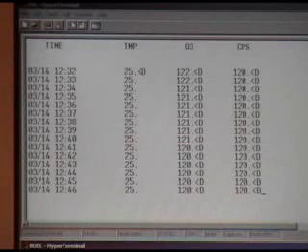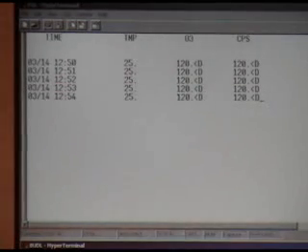We see that our level 3 readings are looking good. Past 5-6 minutes, it's leveled off right at 120, and we'll probably be taking readings at 12:50. We've got our 5 consecutive readings, and we have copied them down to the logbook. Now it's time to run the 70 ppb event for level 2.